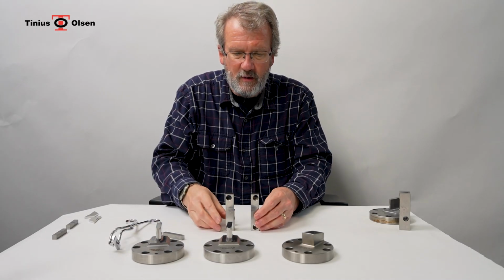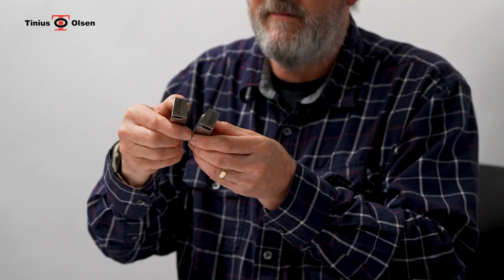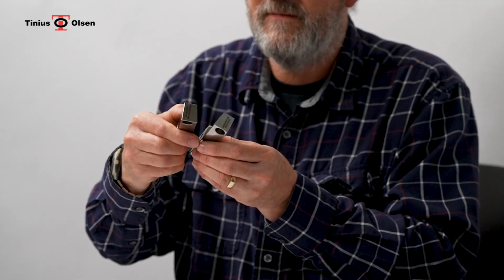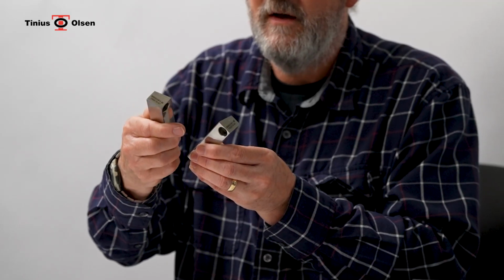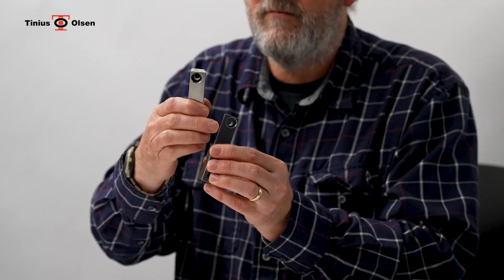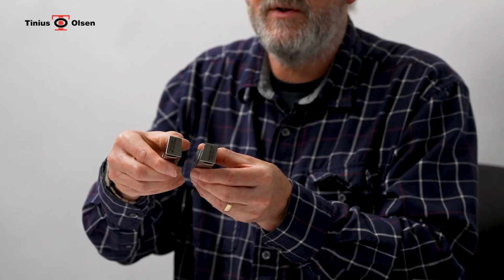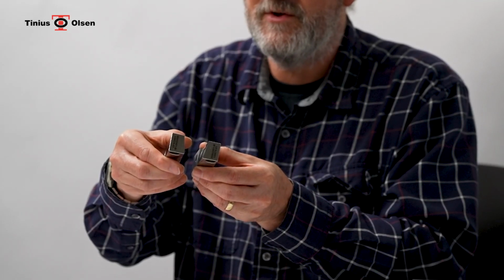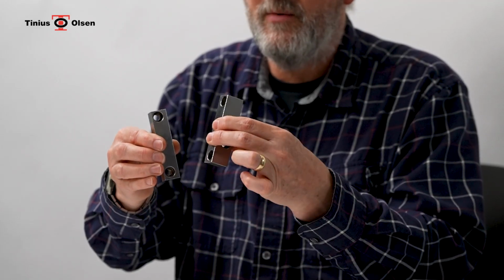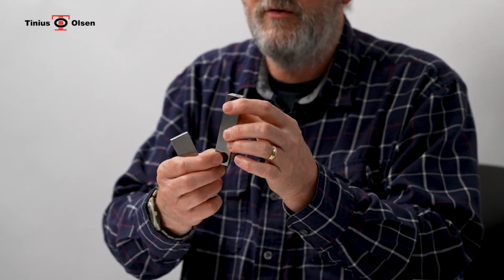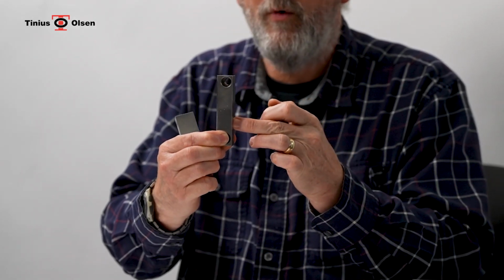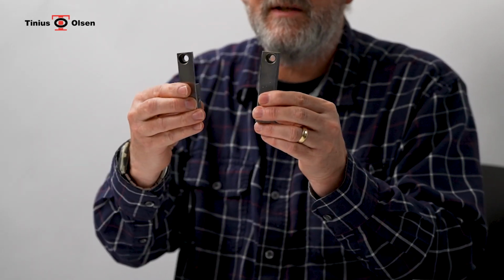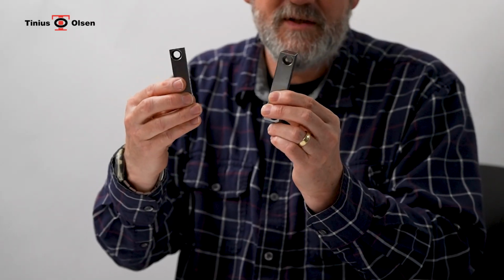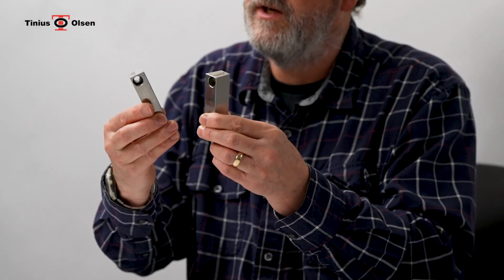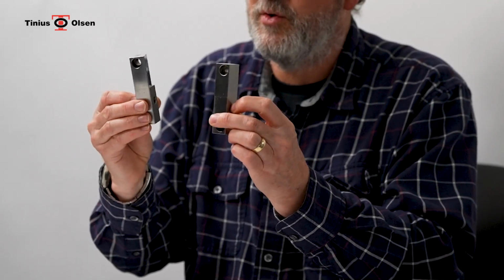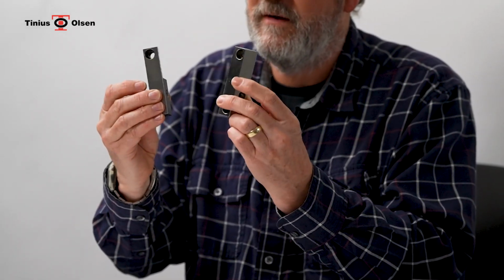The anvils themselves, these are common for both ASTM and ISO, and these are new anvils. You can see there's quite a nice radius on here that covers the entire distance, and they are recessed across the back so that the sample does not get wedged between the anvils during a test. There are 3 mounting bolts per anvil. There are 2 which locate it back against the machine, and 1 which actually holds it to actually set the spacing on the anvils. This spacing is tightly controlled by the body of the machine itself, therefore ensuring that these are torqued to the correct spec in the correct order is very important.